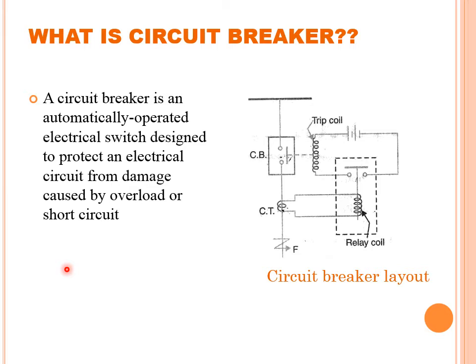At the instant of breaking, an unwanted phenomenon called arc is developed. There is a large electromagnetic discharge associated with the performance of a circuit breaker, requiring more elaborate engineering compared to simple switches. In the relay circuit layout, the line to be protected has a current transformer with its primary in series with the line. The secondary of the CT is connected in series with the relay coil, and the relay contacts are part of the trip circuit of the circuit breaker.